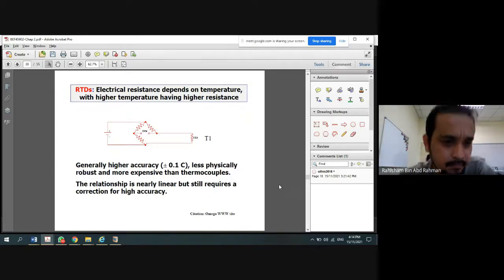Okay, what is RTD? RTD is again a temperature-based sensor, which is a resistance thermal detector. This is used based on the electrical resistance. Of course, the electrical resistance depends on the temperature. The higher the temperature, the higher the electrical resistance. So by using this concept, we can use the RTD device as a temperature sensor, so that we can measure the temperature of a certain device.